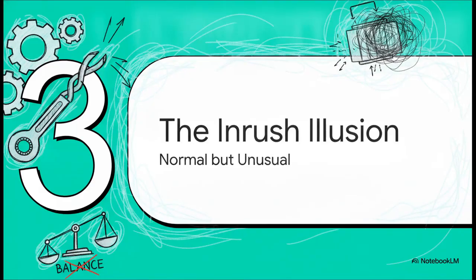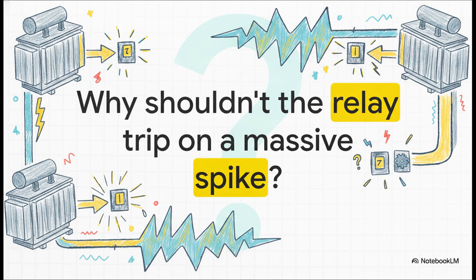So that brings us to Section 3, the inrush illusion. Here is what most people new to protection get wrong. Let's do a quick interactive moment. Think about this for a second. Imagine a completely cold transformer is suddenly energized. When that switch is thrown, the transformer draws a massive, violent spike of current from the network. From the outside, it looks exactly like a catastrophic internal fault. So why shouldn't the relay instantly trip the breaker and shut it all down?